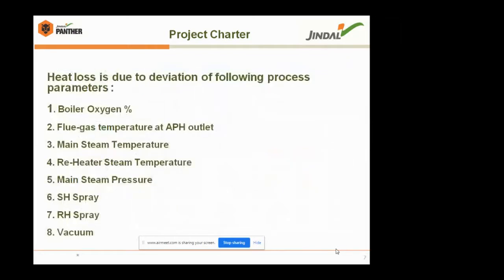As shown in my earlier sheet, in boiler efficiency, if we increase the oxygen by 2%, then the boiler efficiency will reduce by 1%. And in case of flue gas temperature, if we increase the flue gas temperature by 20 degrees from design, then the boiler efficiency will again reduce by 1%.